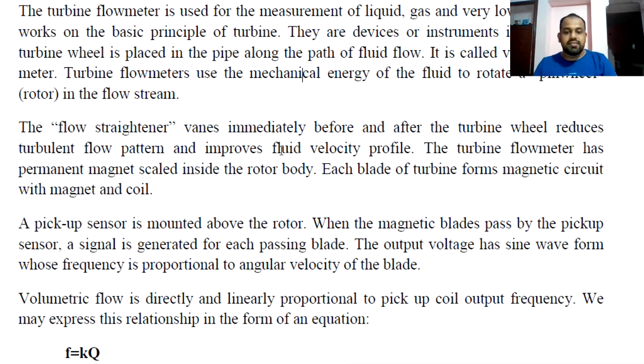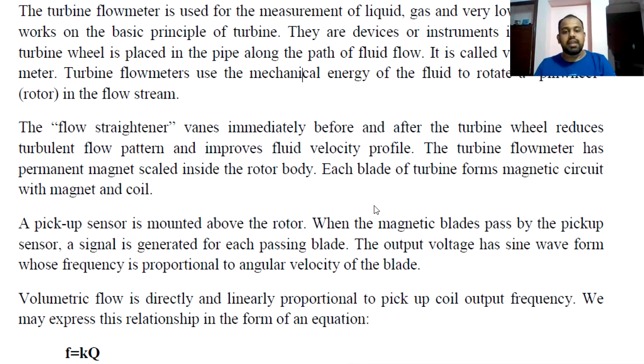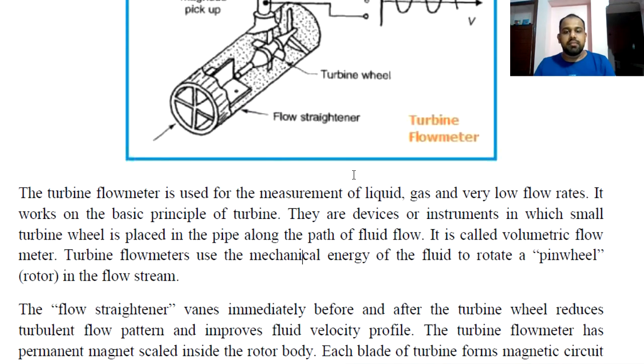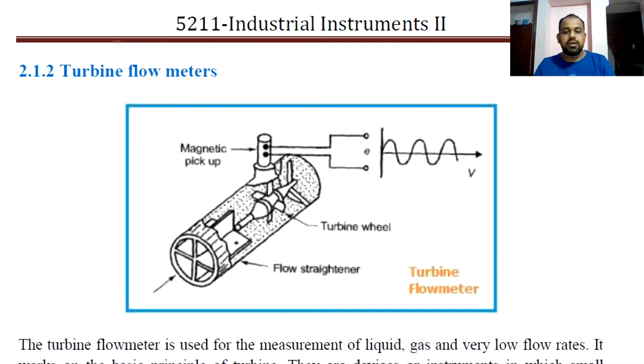The flow straightener vanes immediately before and after the turbine wheel reduce the turbulent flow pattern and improve the fluid velocity profile. The turbine flow meter has a permanent magnet sealed inside the rotor body. Each blade of the turbine forms a magnetic circuit, and the turbine wheel itself is made of magnetic material.